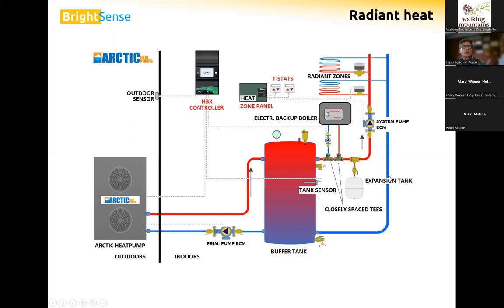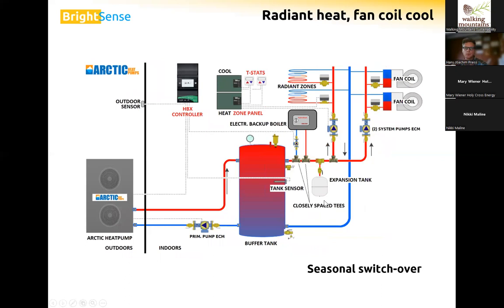The thing is, it's also slow. Bringing the temperature of your floor down takes time. And so people do it here on the front range, and it works really well when we have 100 degrees and we can run the radiant cooling for weeks on end. But in a mountain town, if you only need a little bit of cooling for 2 hours, maybe in the late afternoon, my recommendation would be a point source fan coil in those particular rooms that tend to overheat when you can't open the windows at night. This is what that would look like. The fan coils on a separate circuit over here, but connected to the same buffer tank.